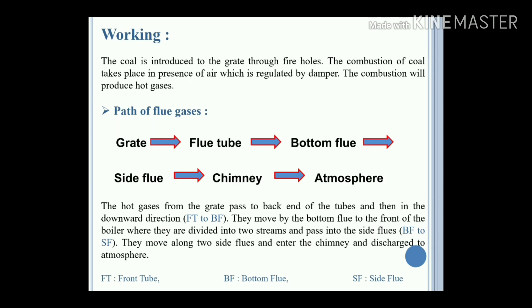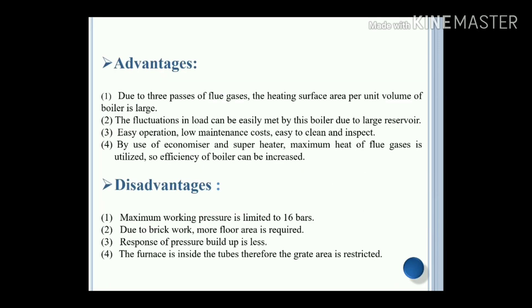The hot gases from the grate pass through the back end of the tubes, then move in a downward direction through the bottom flue to the front of the boiler, where they are divided into two streams and pass into the side flues. They move along the two side flues, enter the chimney, and are discharged to the atmosphere.